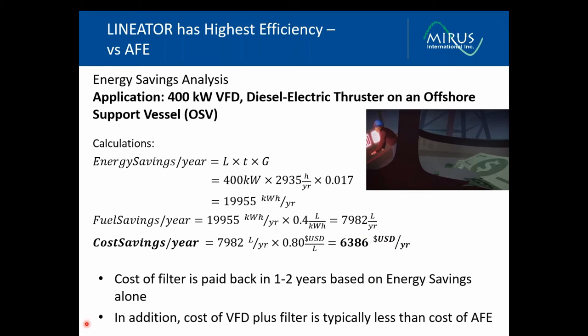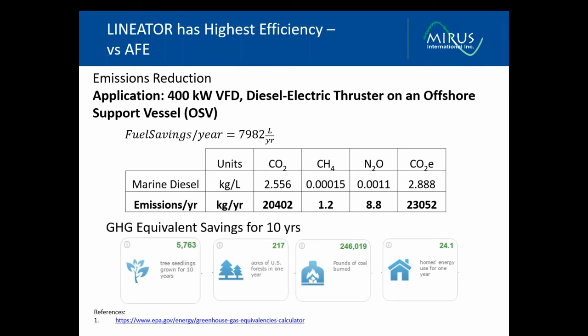This savings would provide a payback of less than 2 years on the filter alone, but of course the combined package of a filter and a six-pulse drive compared to an AFE drive is less expensive. So there's a savings just in that install cost as well. And of course, if you're reducing your fuel consumption, you are improving the environment, lowering the emissions and the greenhouse gas emissions and so on.